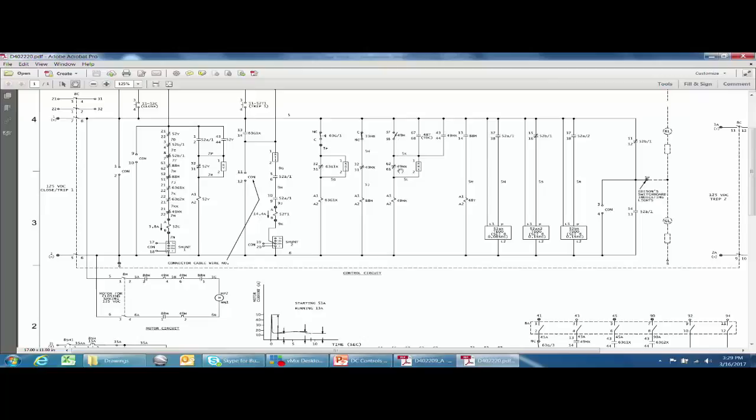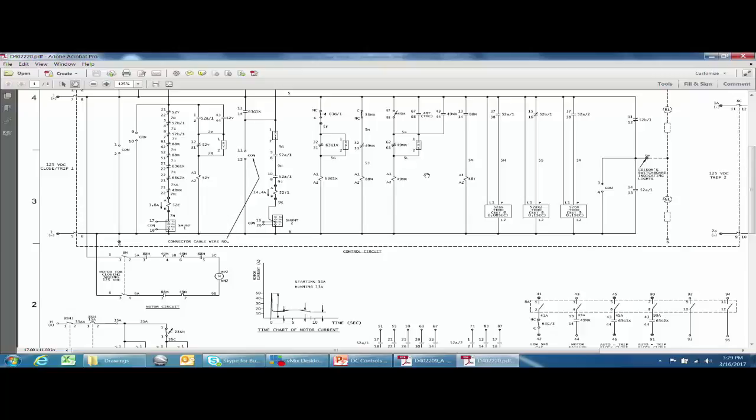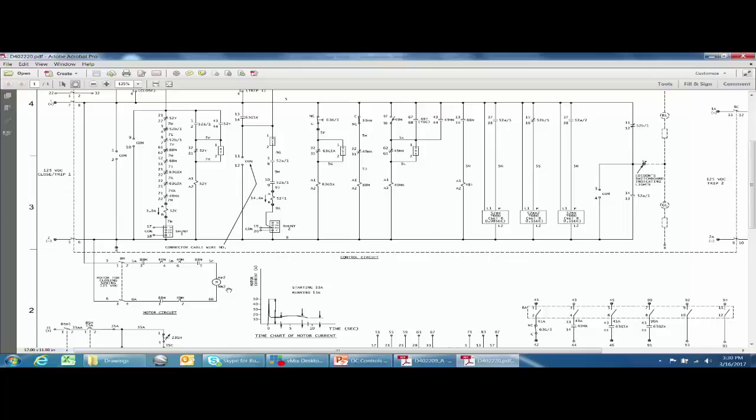The final device shown is the 49M and its MX contact, which comes out of this logic. These are the various relays that protect the motor — among them a thermal relay. If there's something wrong with the motor and it cannot recharge that breaker, we do not want to close the breaker.